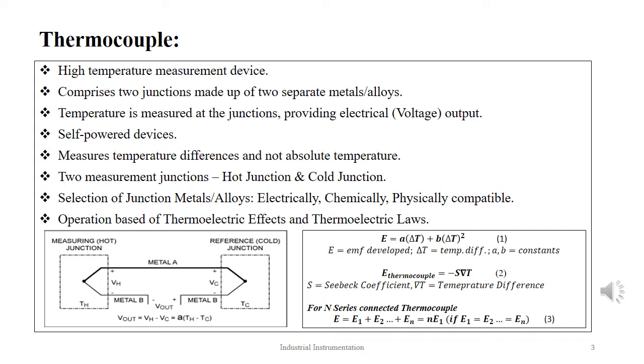The voltage generated is interpreted using the thermocouple reference table to calculate the exact temperature values. The thermocouples do not actually measure absolute temperature, and the temperature difference between the junctions, that is the hot junction and the cold junction, is measured. The resultant voltage is given by the Seebeck effect equation as shown in equation 2 below. As we see here, the voltage generated is proportional to the temperature difference.